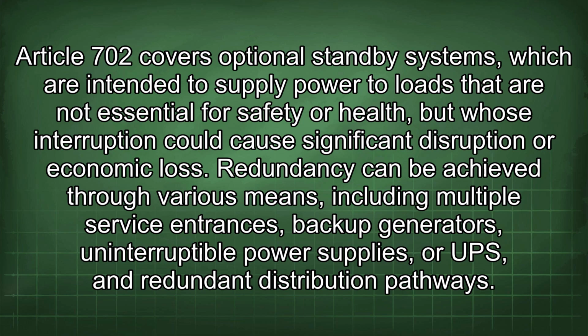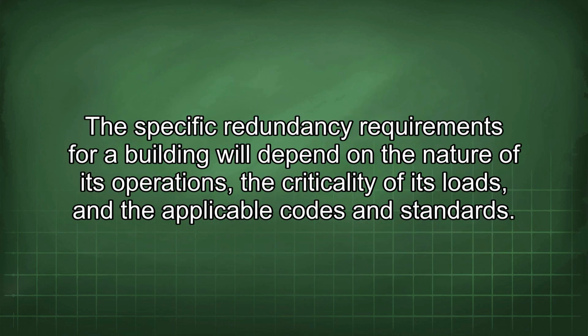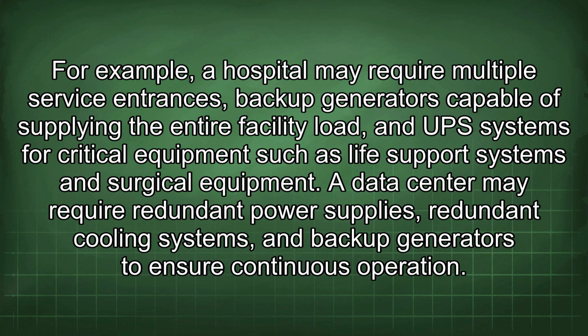Redundancy can be achieved through various means, including multiple service entrances, backup generators, uninterruptible power supplies, or UPS, and redundant distribution pathways. The specific redundancy requirements for a building will depend on the nature of its operations, the criticality of its loads, and the applicable codes and standards. For example, a hospital may require multiple service entrances, backup generators capable of supplying the entire facility load, and UPS systems for critical equipment such as life support systems and surgical equipment.